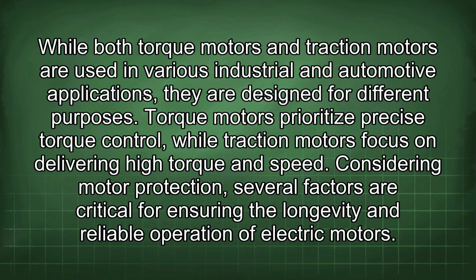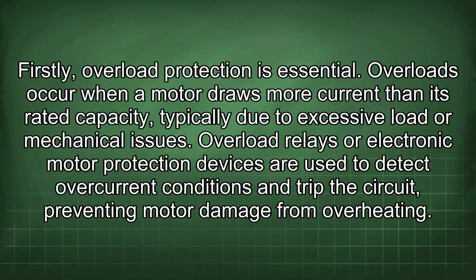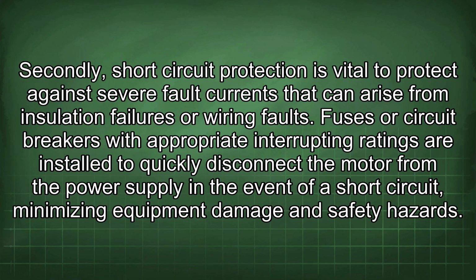Considering motor protection, several factors are critical for ensuring the longevity and reliable operation of electric motors. Firstly, overload protection is essential. Overloads occur when a motor draws more current than its rated capacity, typically due to excessive load or mechanical issues. Overload relays or electronic motor protection devices are used to detect overcurrent conditions and trip the circuit, preventing motor damage from overheating. Secondly, short-circuit protection is vital to protect against severe fault currents that can arise from insulation failures or wiring faults. Fuses or circuit breakers with appropriate interrupting ratings are installed to quickly disconnect the motor from the power supply in the event of a short circuit, minimizing equipment damage and safety hazards.